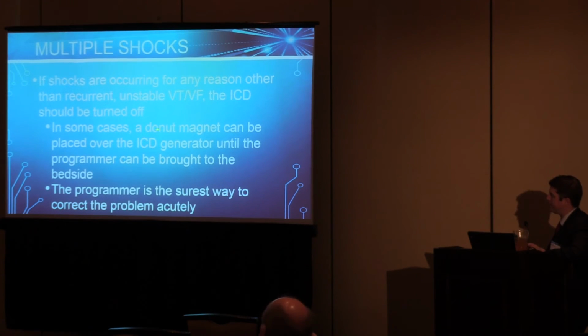one of the important things to know how to do is to place a magnet over the ICD itself. I know that brings some hesitancy, and I've had it from our internal medicine residents and sometimes even more advanced trainees than that. On all of our modern ICDs, this will not inhibit the pacing therapies. That's a key consideration. If you have a patient that has complete heart block or is pacer dependent and also has an ICD, you can disable the tachytherapies without disabling the pacing therapy. So if you feel like the shocks are inappropriate and you want to make them stop, a magnet will only stop the tachytherapies, not the pacing.